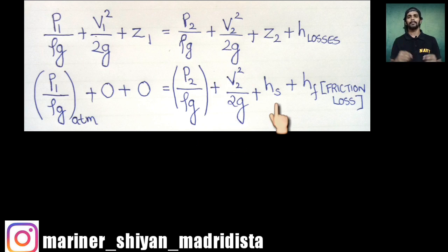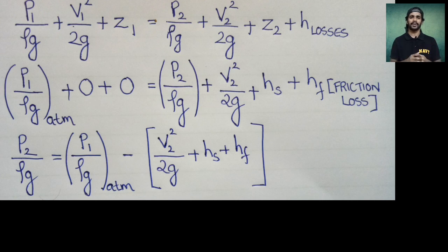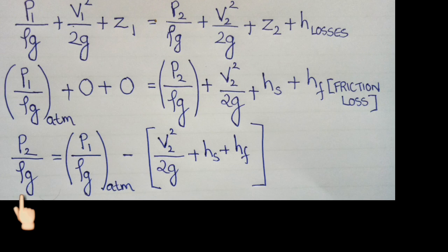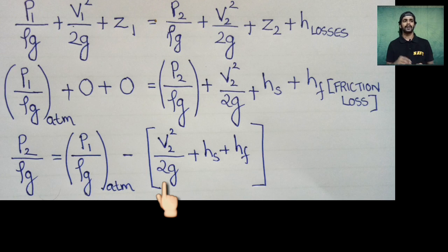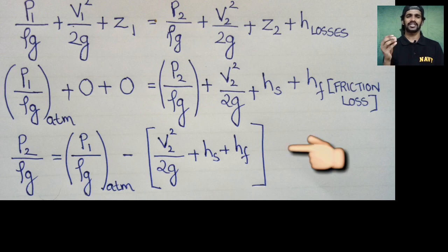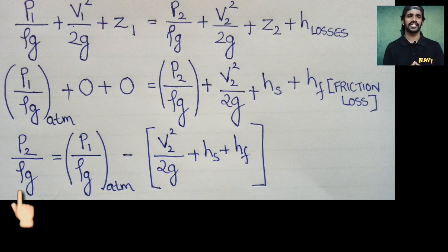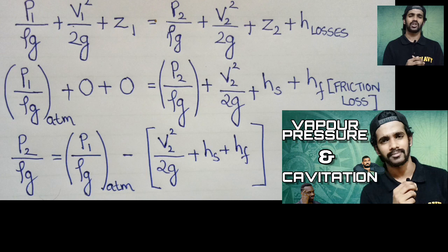The full equation becomes: P1/ρg + 0 + 0 = P2/ρg + V2²/2g + Hs + friction loss. Now we solve for the pressure at the eye of the impeller: P2/ρg = P1/ρg (atmospheric pressure) minus the bracketed terms. Therefore, the pressure at the eye of the impeller, P2/ρg, will always be less than atmospheric pressure.